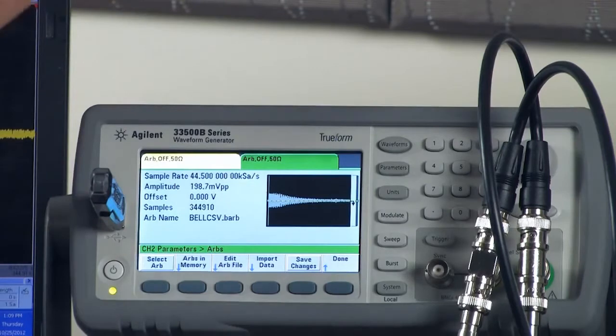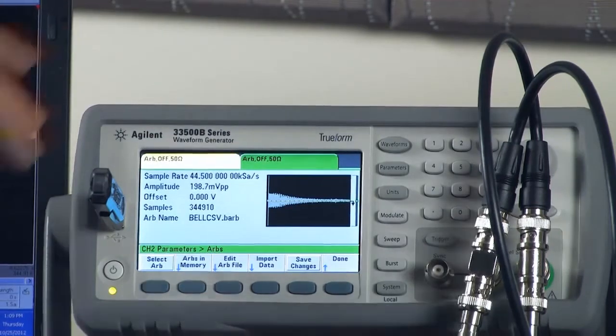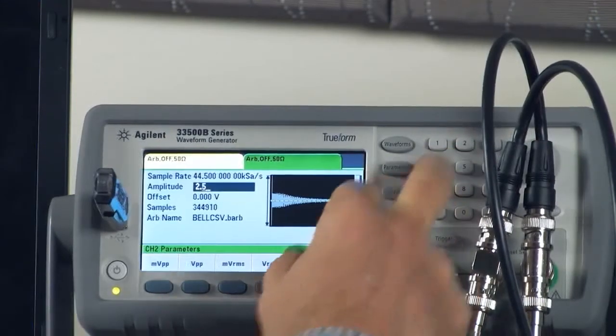Okay, so the bell loaded, and it came in with a certain amplitude that was set over on the PC. I'm going to change the amplitude right now - 2.5 volts at 44.5 kilohertz.